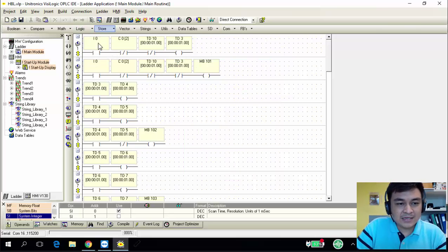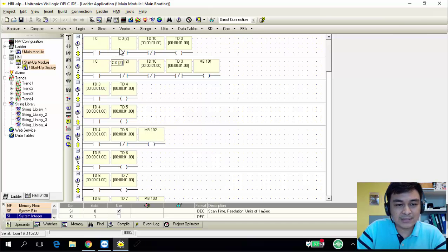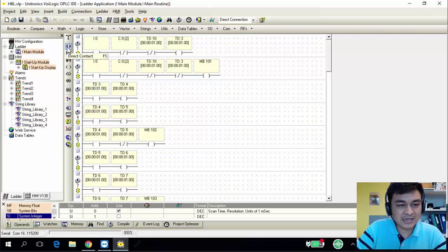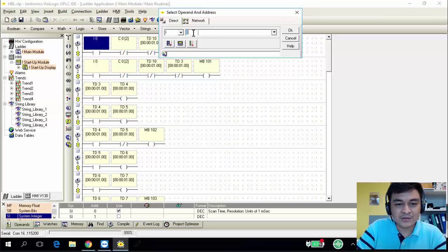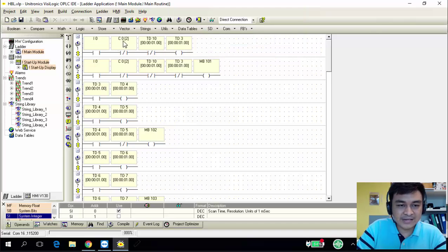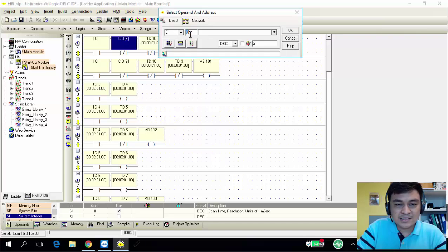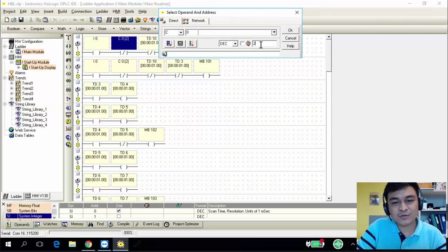I'm going to use I0 as an input switch to start my number display. To get I0, click on the direct contacts and use I0, then click OK. Next, I'm using C0 — C0 is a counter. Choose the inverted contact. C0 is the counter number, and the value is 2 because I'm looping for two times. This inverted contact means after the counter has counted two times, it will cut off the connection.